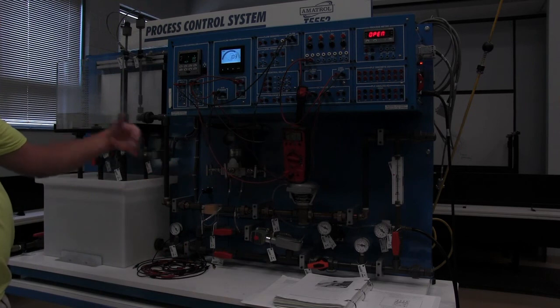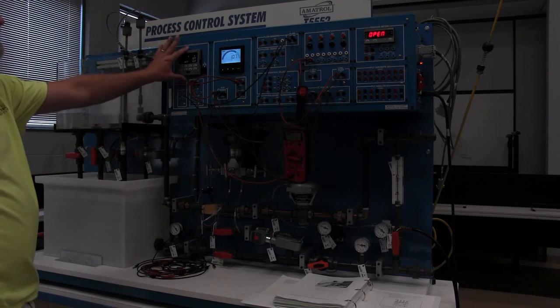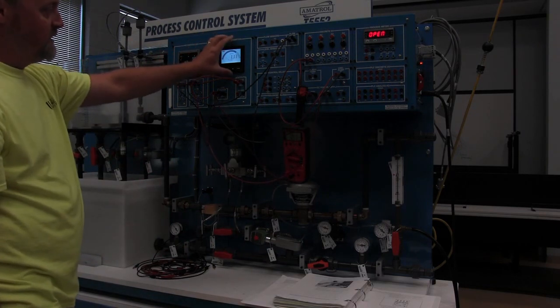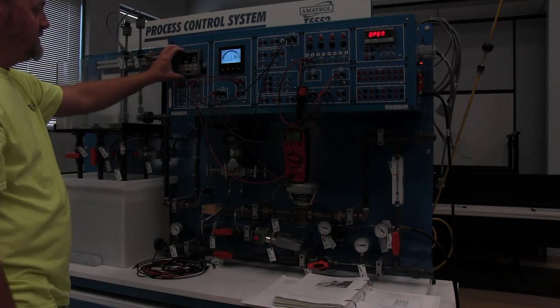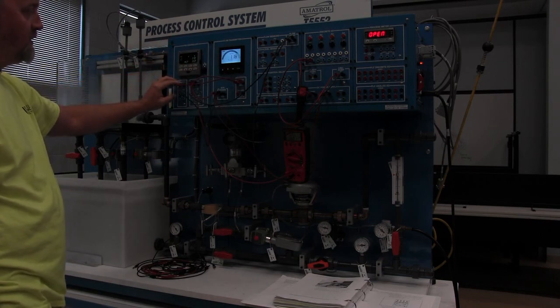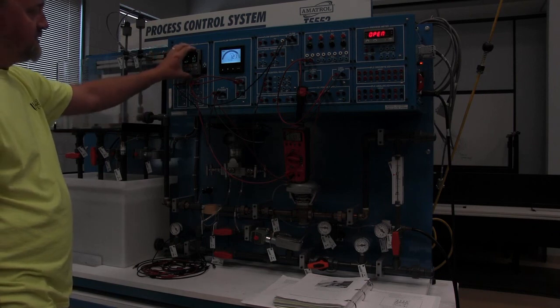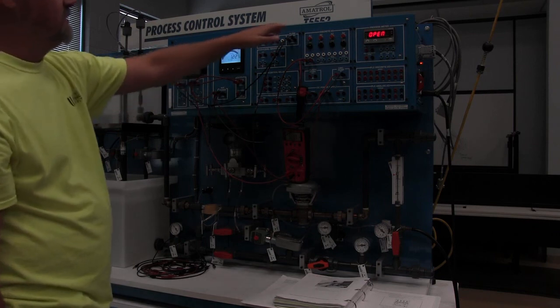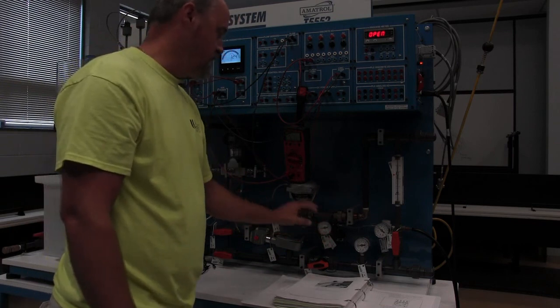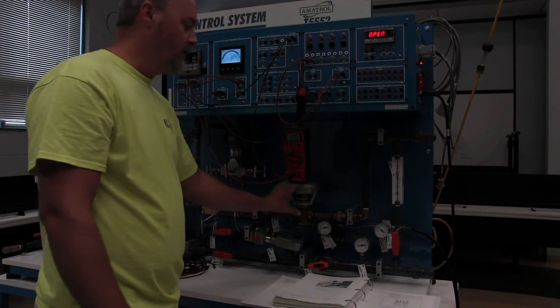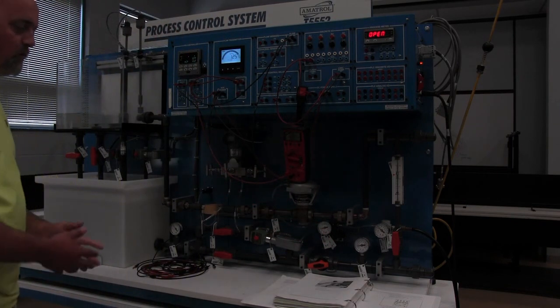It's opening that valve and closing that valve as needed based off of this flow meter giving this Honeywell an analog input of what the flow is, and then this Honeywell is outputting an analog signal to the I/P, which is converting it to pressure to open and close this valve to know where it needs to be.